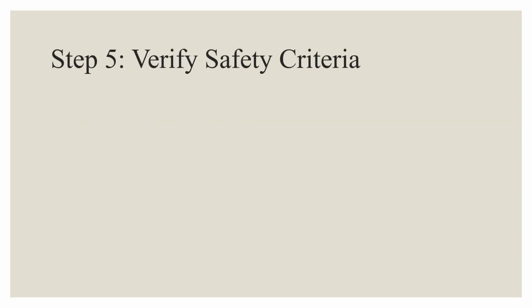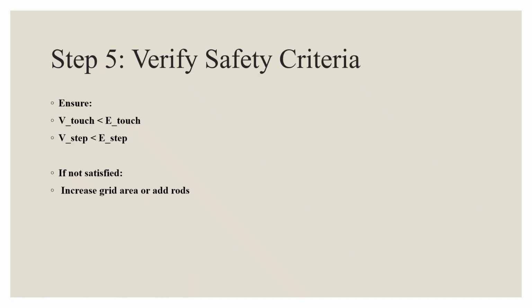The fifth step in the design is to verify safety criteria. We have to ensure that touch voltages and step voltages are within the tolerable limits. If they are not, then we can improve the design by increasing grid area, adding vertical rods, reducing soil resistivity with chemicals, or using a gravel surface layer to increase insulation.